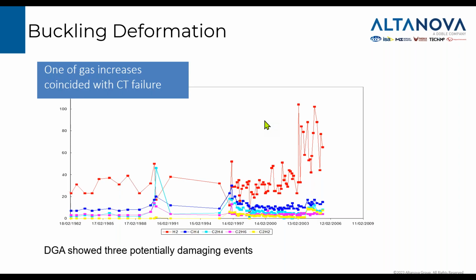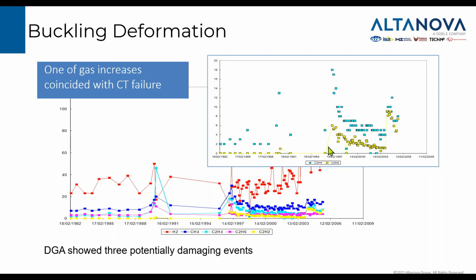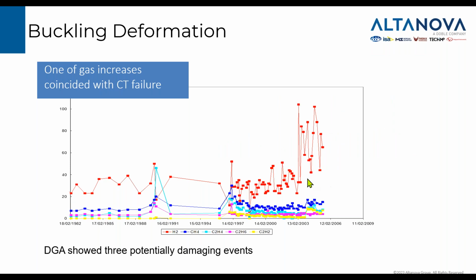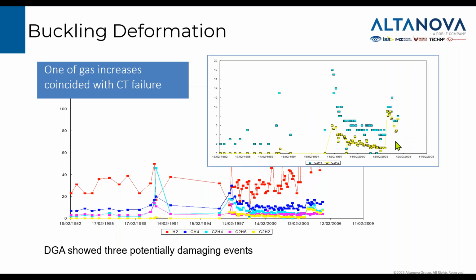So this was the DGA. If you look more carefully, you will see there were at least 2 events. This is acetylene and ethylene only, and here before we have all other gases, including hydrogen, which was rising. So this was a driver for the customer to decide it would be tested. As we look closer at ethylene and acetylene, we can see at least 2 events in which they rapidly rose, then decreased, and rose again, decreasing. There was something similar in the past as well, to much lower extents. One of these events coincided with a CT failure somewhere in the system.